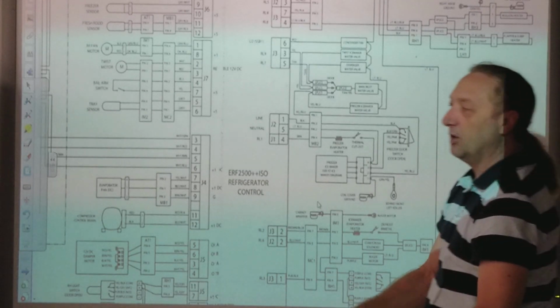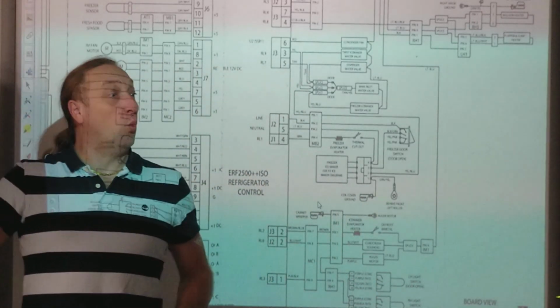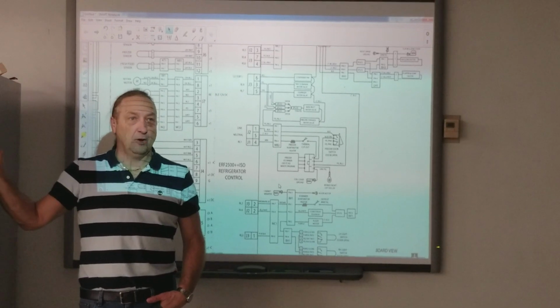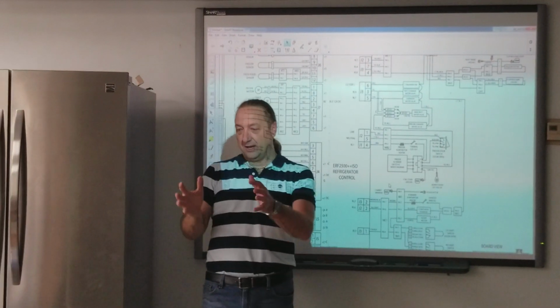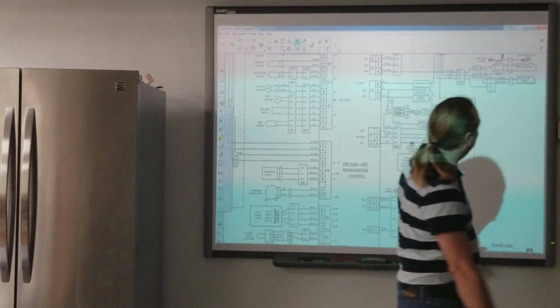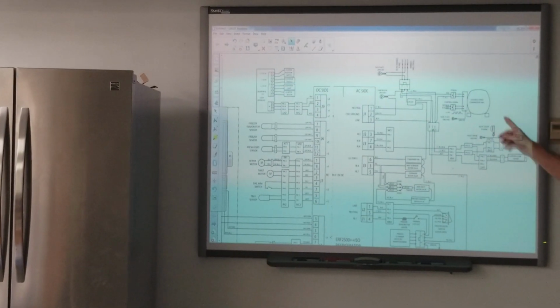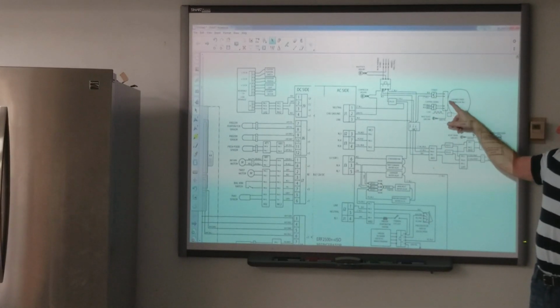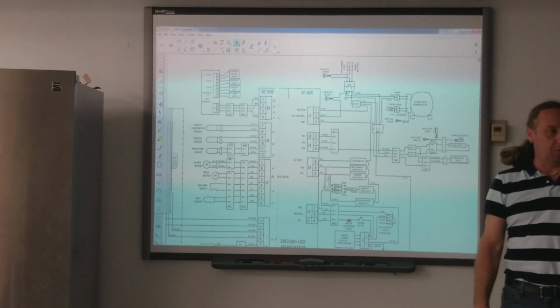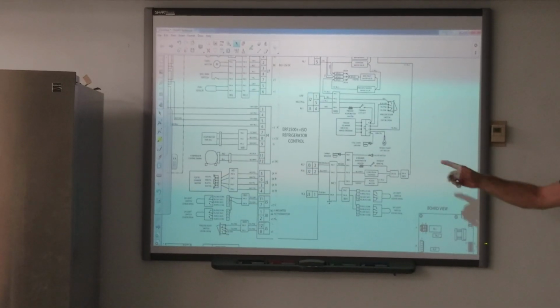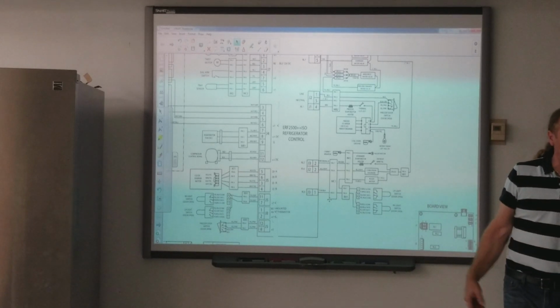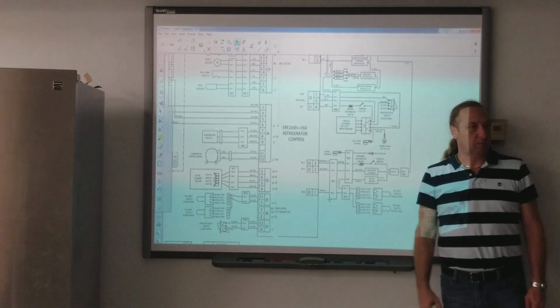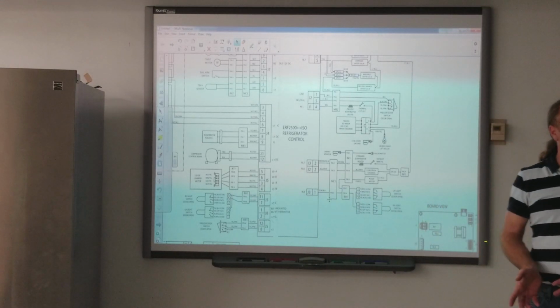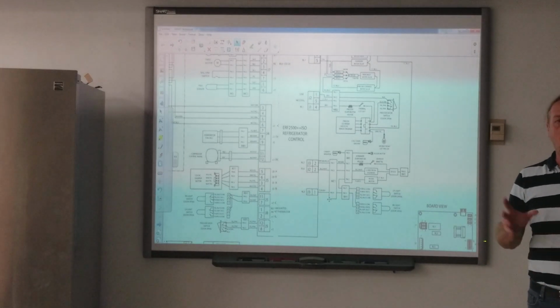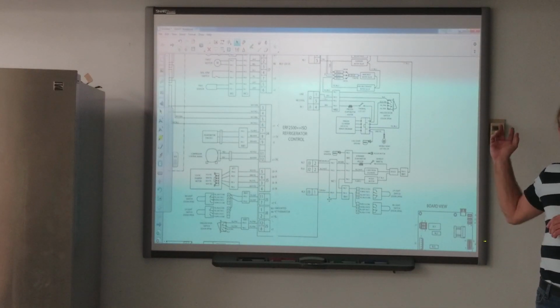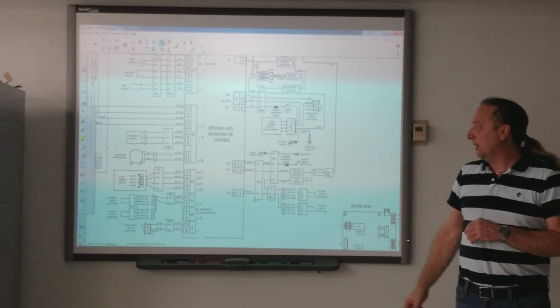No, because this particular brand of refrigerator could have one or the other compressor. Those of you familiar with refrigerators, you have a standard compressor with a relay and an overload. If we look at this diagram, this will be the compressor, this is power coming in, the relay and overload would be here. That would be like a standard compressor, okay? The other one would be a variable speed compressor. If it was a variable speed compressor, it would be running off of these wires here. So if it has an AC volt compressor, just a standard non-variable speed compressor, it would be on the AC volt side. If it was on this side, it'd be running off of there.